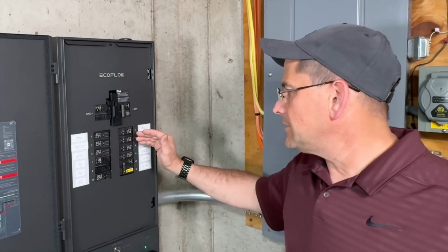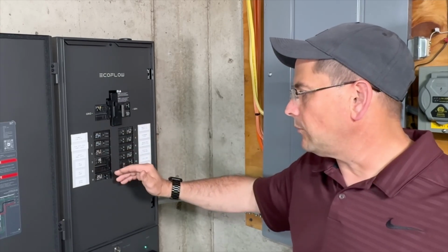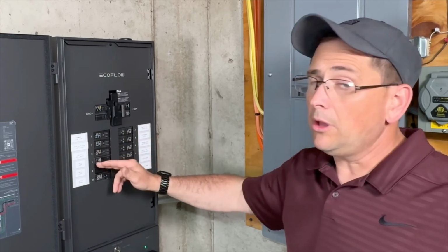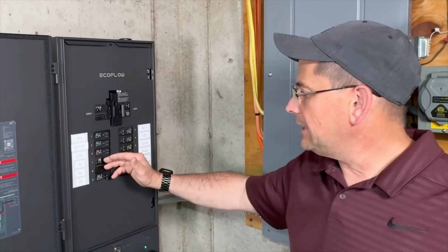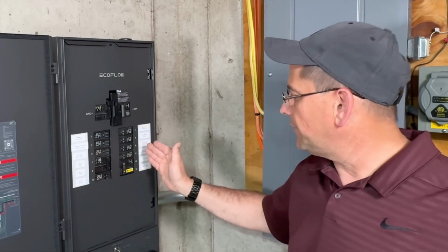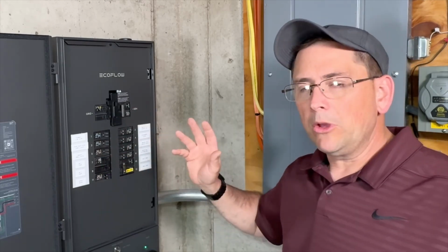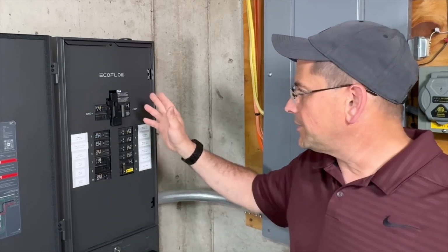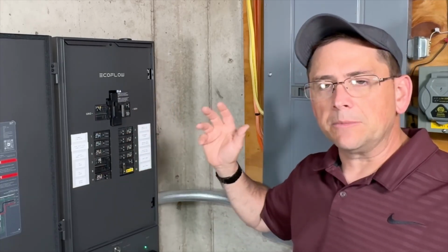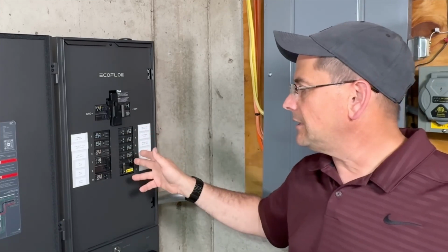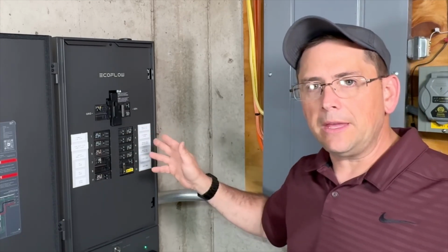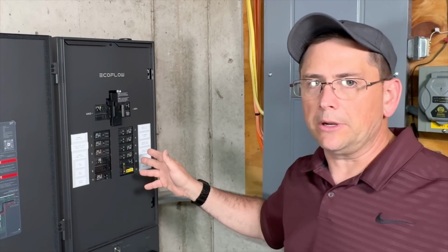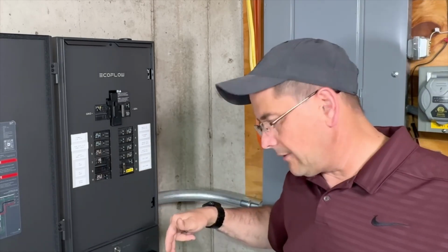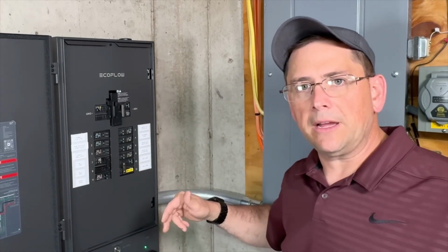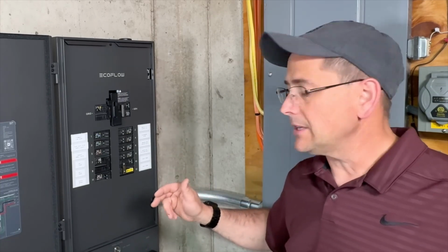Now, the thing you're going to run into is when you have all these other circuits running, whether it be the furnace, the well has quite an inrush. So when it kicks on, it spikes way up there. Same thing with my heat pump. In the next video that I did, where I showed me installing this and actually putting things together, I actually measured my inrush values on it, and the heat pump actually pulls about 52 amps instantaneous. That's where the inverter system down here that can run 10,800 watts for 10 seconds is able to handle that kind of load.